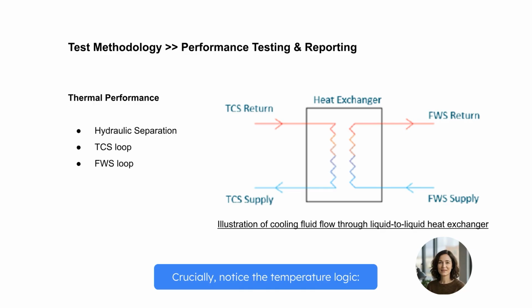Crucially, notice the temperature logic. We must maintain the FWS supply temperature above the dew point. If we run too cold, we risk condensation on the heat exchanger. For low temp operations, a bypass or insulation is mandatory.